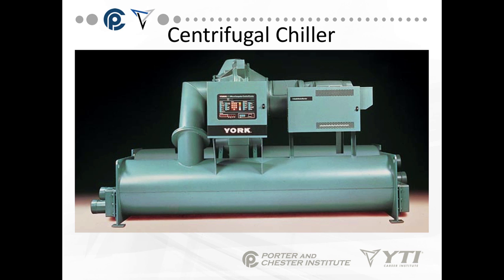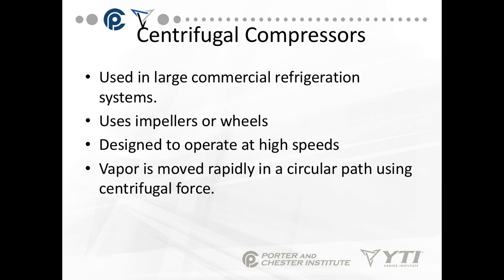This is an example of a centrifugal chiller — yet another type of compressor. It's used in large commercial systems and uses impellers and wheels. It operates at an extremely high speed. Vapors move rapidly in a circular path using centrifugal force — that force that, if you spin something very rapidly, is going to push it in an outward direction.